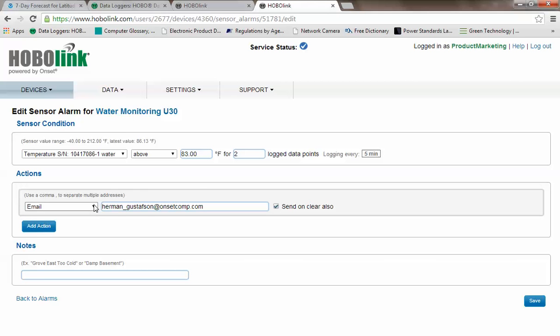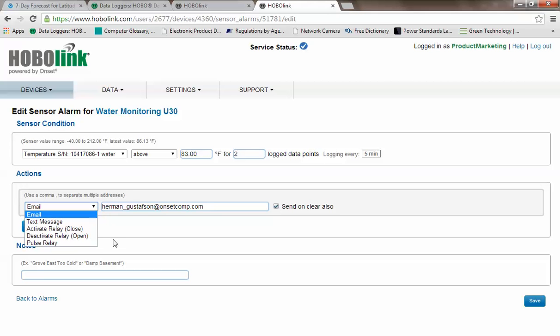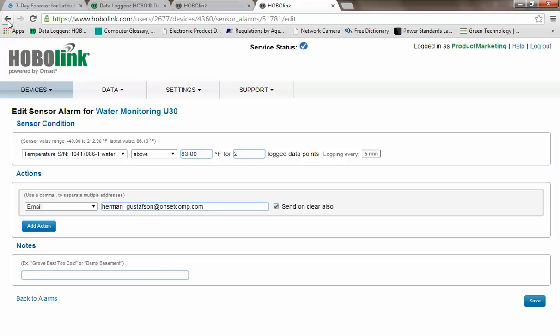And then you can also select how you want to be notified or what kind of action you want to happen. You can select an email, a text message, you can activate the single pole relay, you can close it on the, this again, this is a U30 remote station. You can close the point, you can close the relay, you can open the relay, or you can pulse it. You also have the ability to put in a note in your notification. So if you wanted to be notified, if you want something like close the valve, or turn on the pump, something like that, whatever your notification might be.